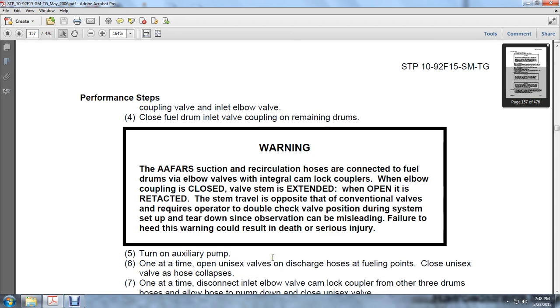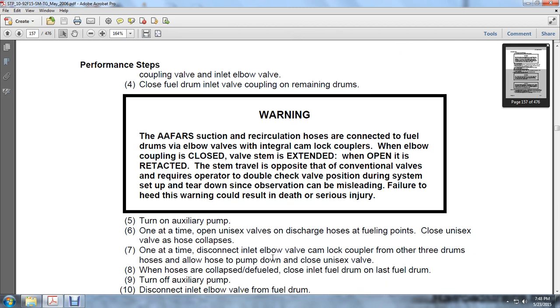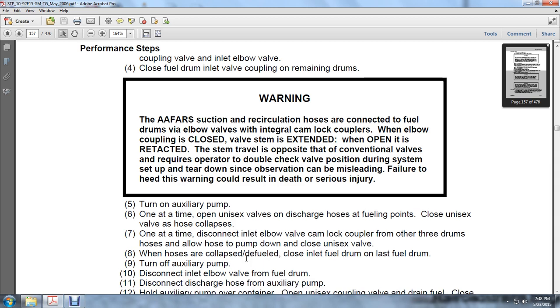Turn on the auxiliary pump. One at a time, open the unisex valves at the discharge of the refueling points. Close the unisex valves as the hose collapses. One at a time, disconnect the inlet elbow valve cam coupler from the other three drum hoses. Allow the hose to pump down and close the unisex valve. When the hoses are collapsed and defueled, close the inlet on the last fuel drum. Turn off the auxiliary pump.